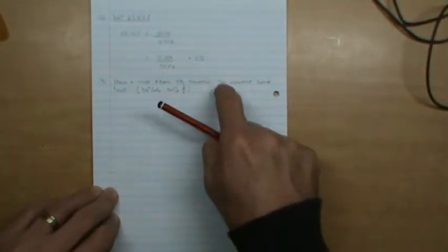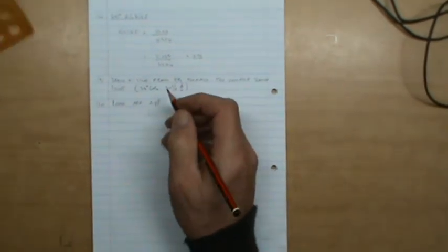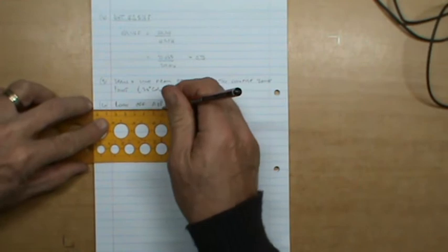And I'm going to come back to this. I'm going to give you another example where there's a variation. Okay, so step 6, you read off the apparatus dew point, and we said the apparatus dew point was 8.6 degrees Celsius dry bulb.